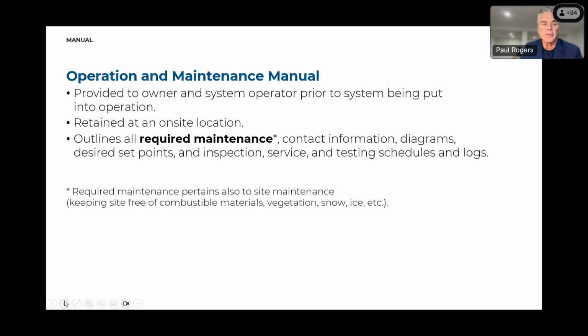The operation and maintenance manual will differ depending on what type of battery energy storage system you're using, so it's something I'd have you take a look at to make sure they're doing things according to the manufacturer's specifications. It outlines the required maintenance, and that word 'required' means it's mandatory—not maybe. That's important during inspections, and any testing schedules and logs should be available for the local jurisdiction.